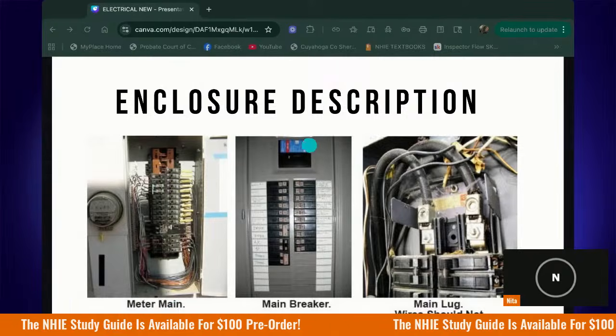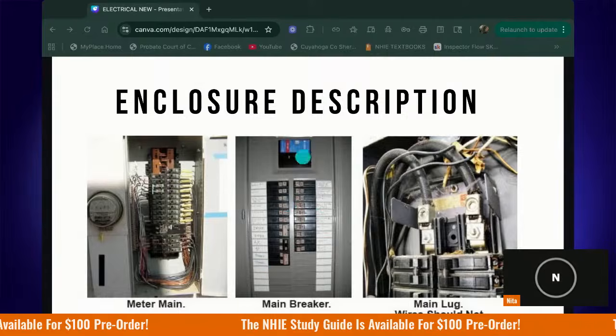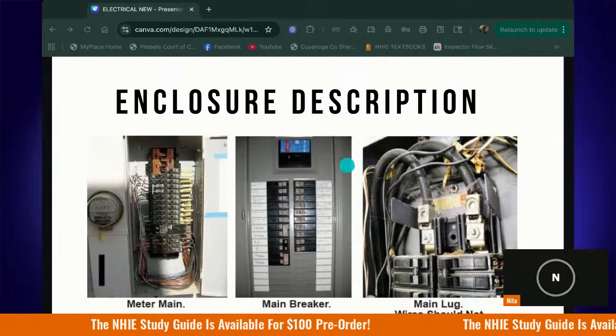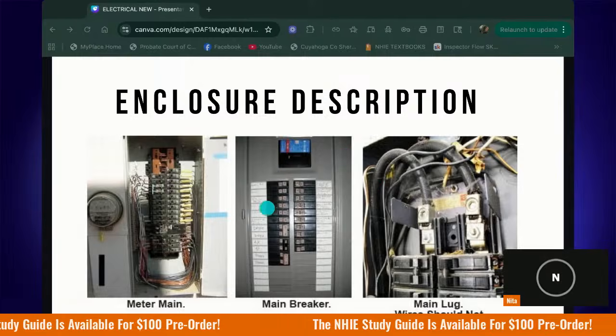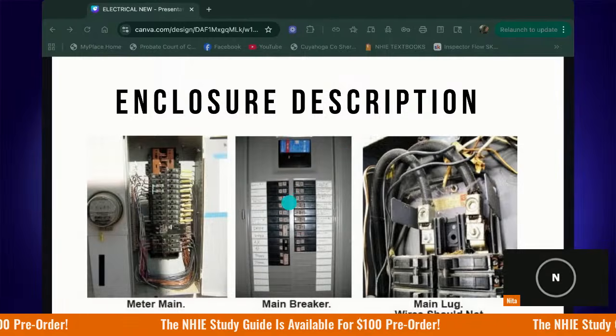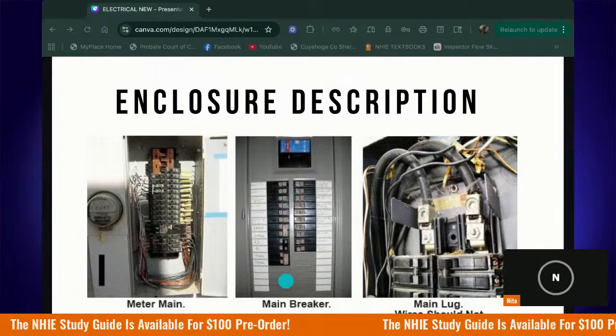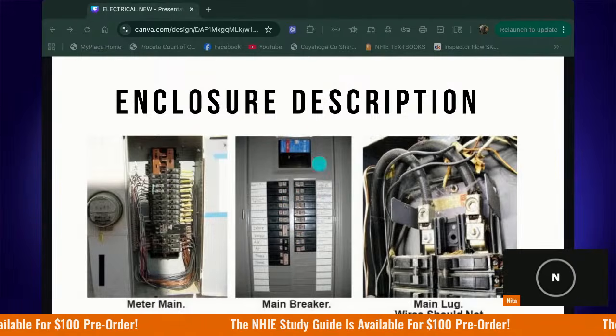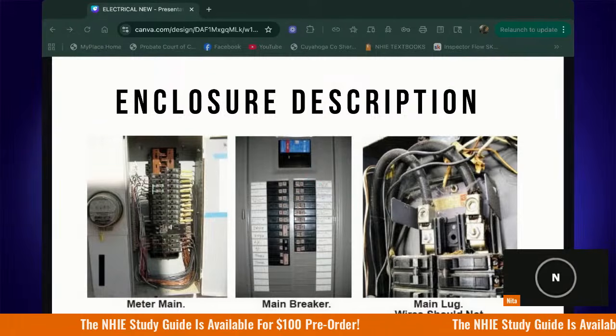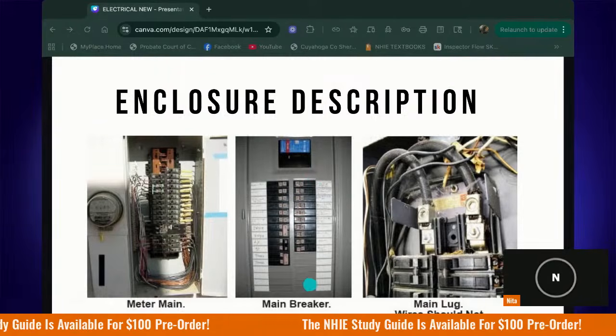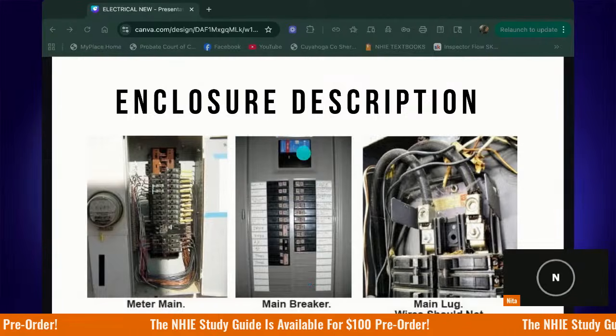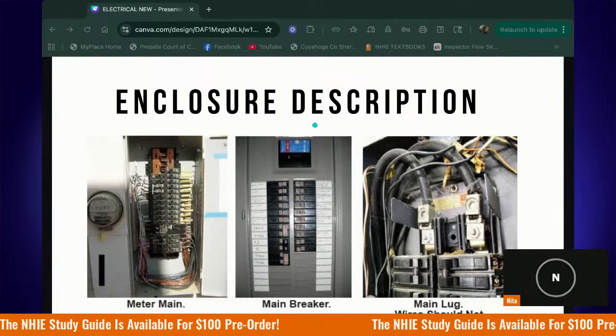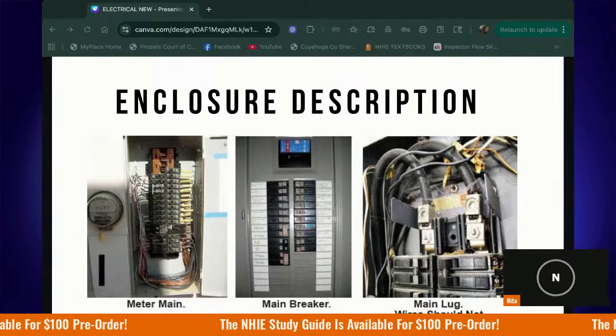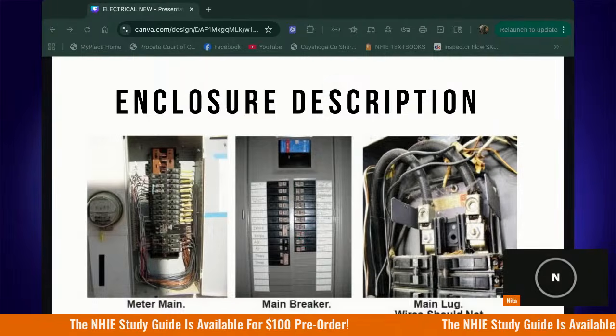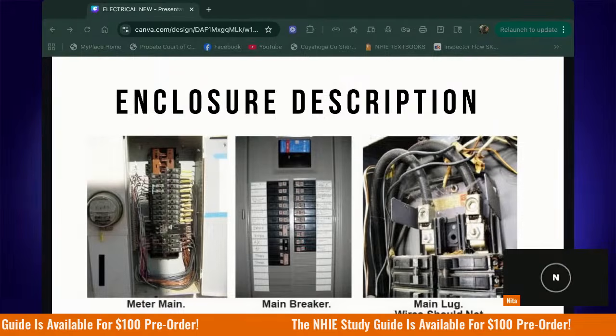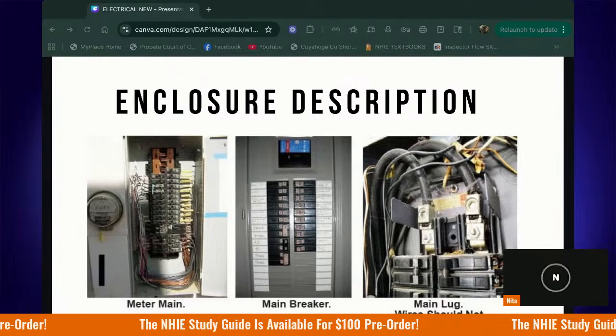This is the most common residential setup, which is this one right here. You have a main breaker or a main disconnect that shuts off all of the power to the home. And then you have all of your branch circuits here that distribute the power to the home. This is most common right now. And then you have your main lug. So the main lug, there's no main breaker inside. So these panels are being fed by another system, essentially, like a sub panel setup.